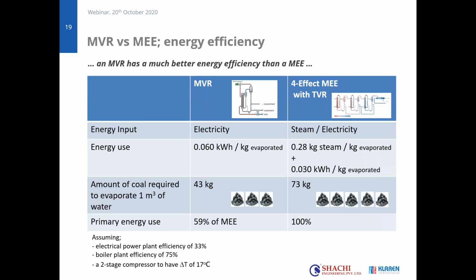And then you would find that for the MVR you need around 40 kg, where for the multi-effect evaporator you would need over 70 kg. So in terms of primary energy, you can save a lot of energy by using the MVR concept. Of course, I realize that in some cases, depending on steam price and electricity price, it is more beneficial to take a multi-effect evaporator, or maybe there is waste steam available. But if that's not the case, then an MVR has the benefit of a better energy efficiency.